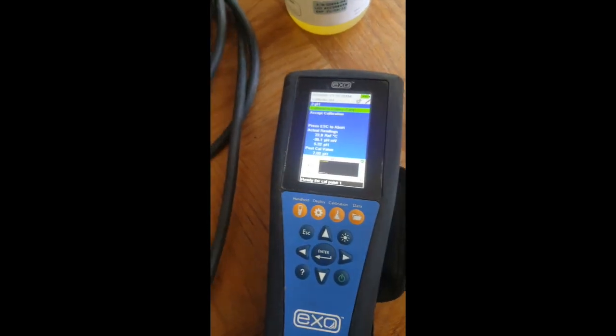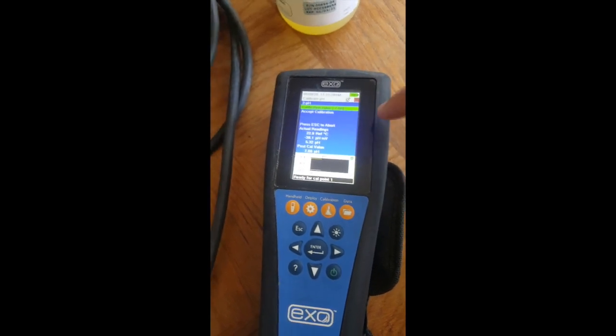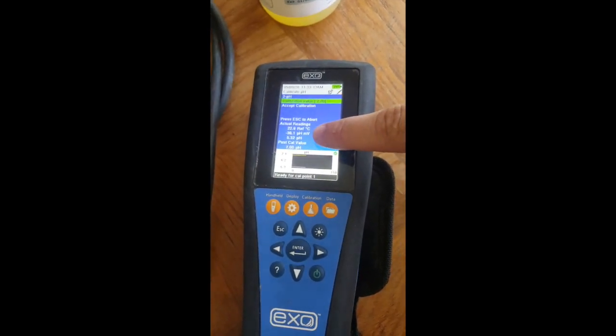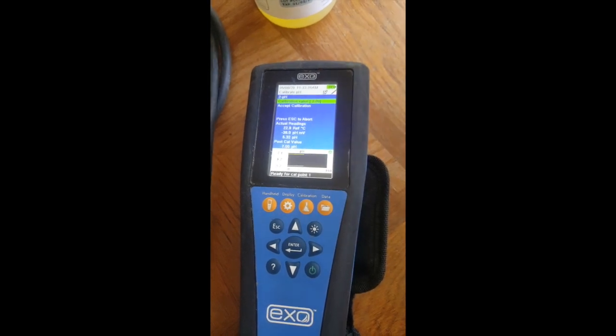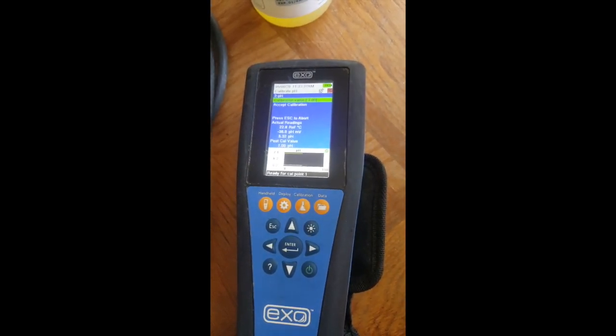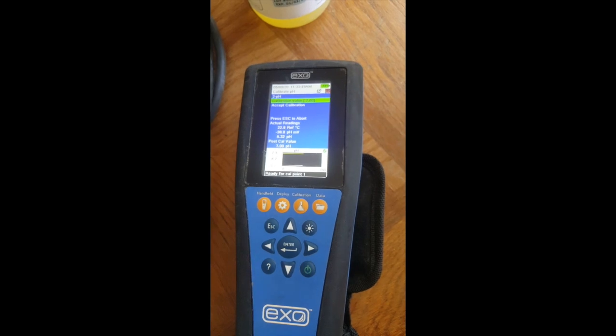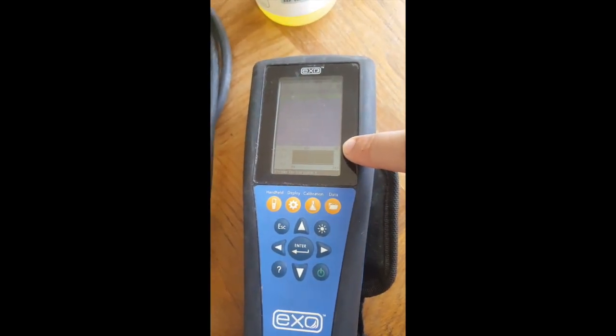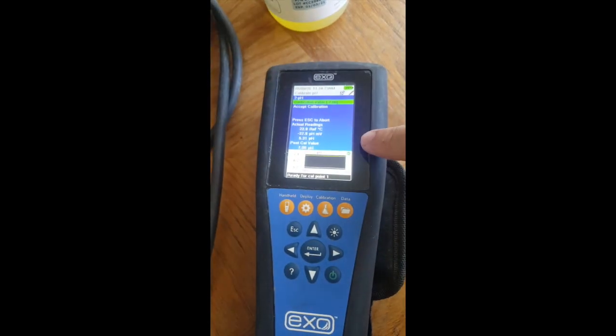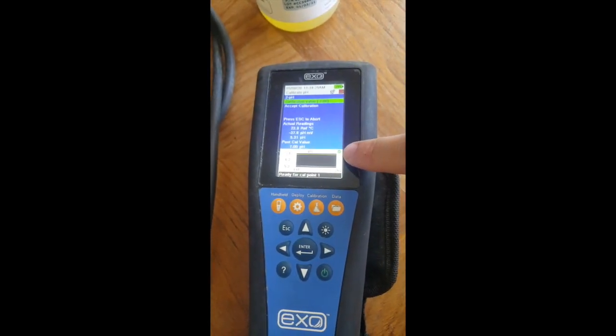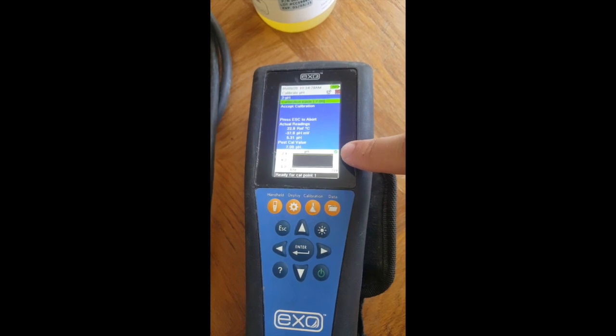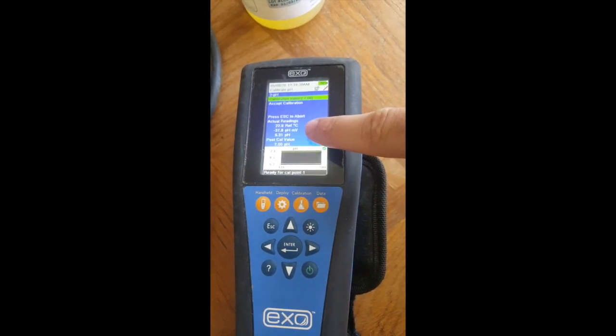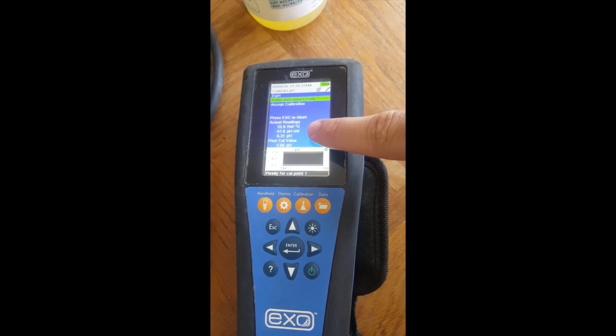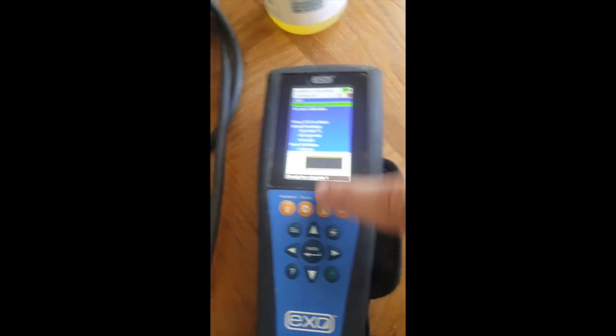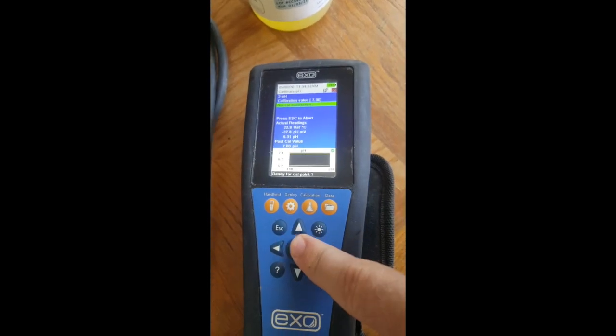Now, after we have set our calibration value, it's always good to watch our pH millivolts right here to see if it keeps fluctuating. We want it to stabilize well. We do have a green check mark, which means the handheld has a QA/QC tester in it, and it's saying that we are good to go. Our millivolts has mostly stabilized, so I'm going to click accept calibration.